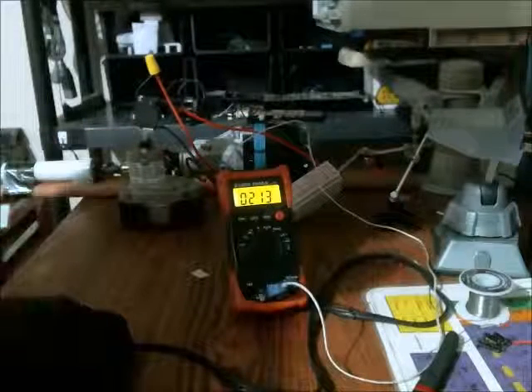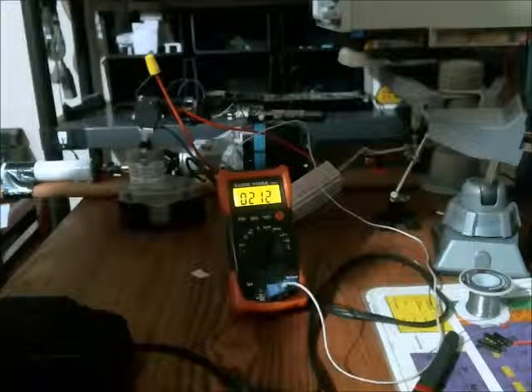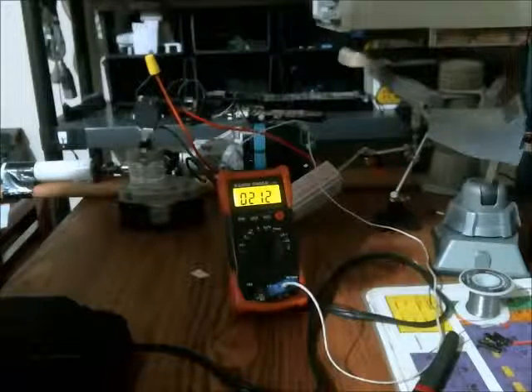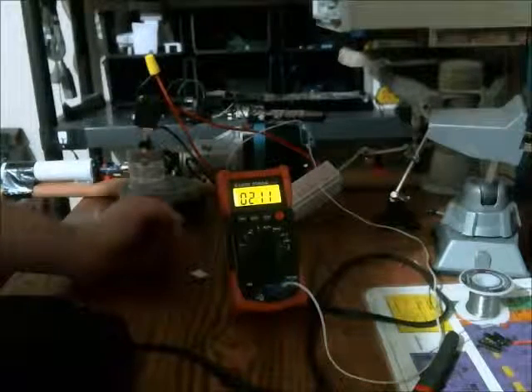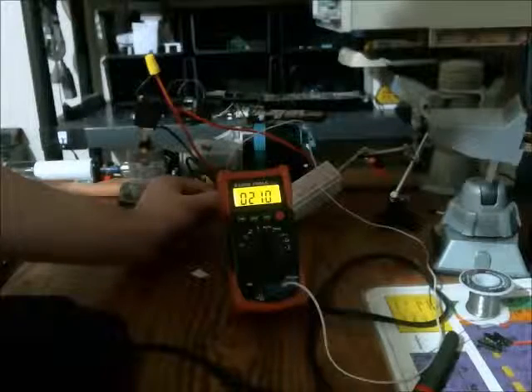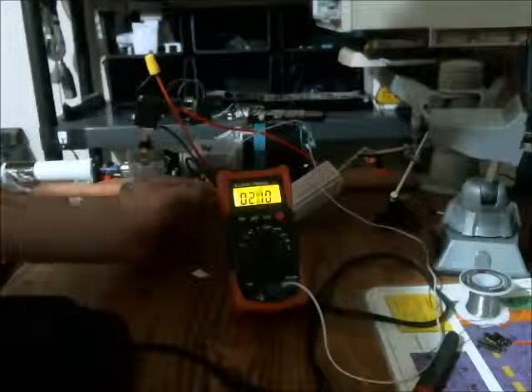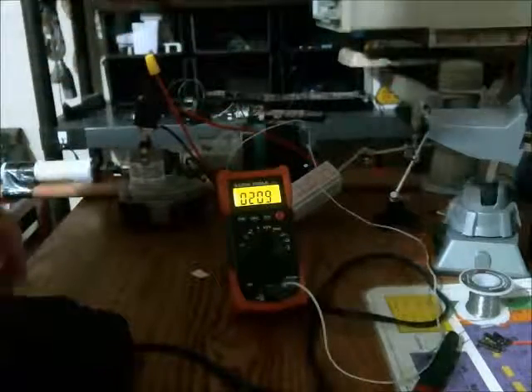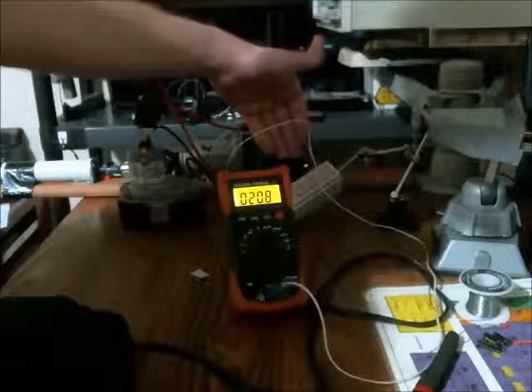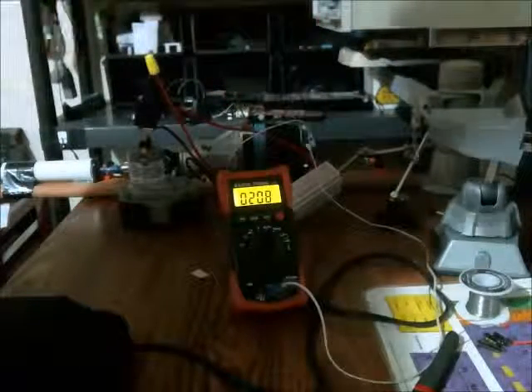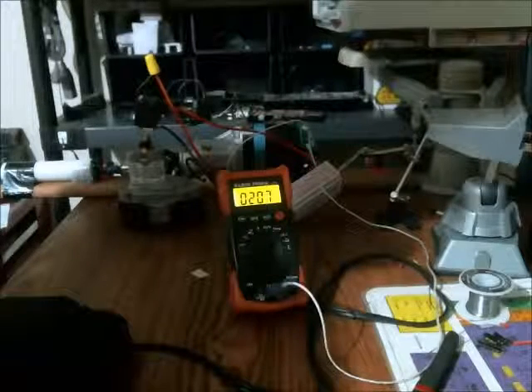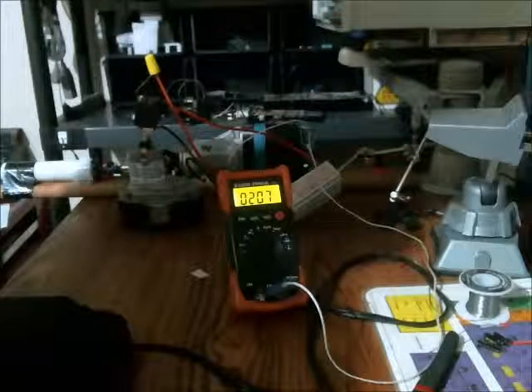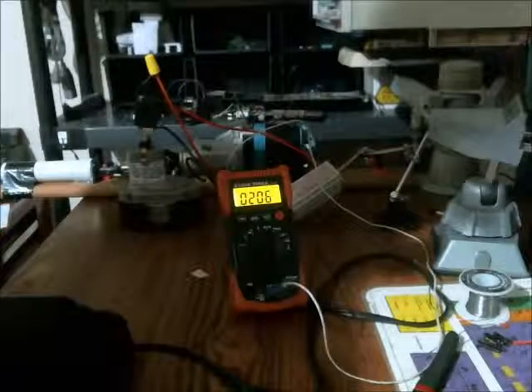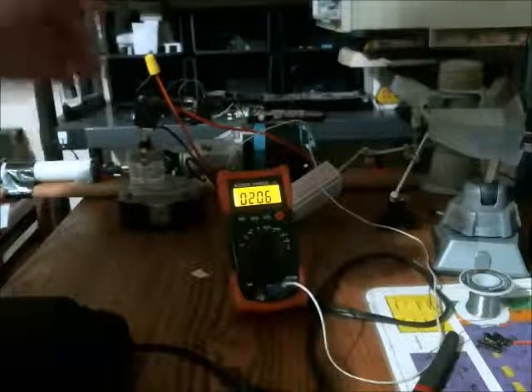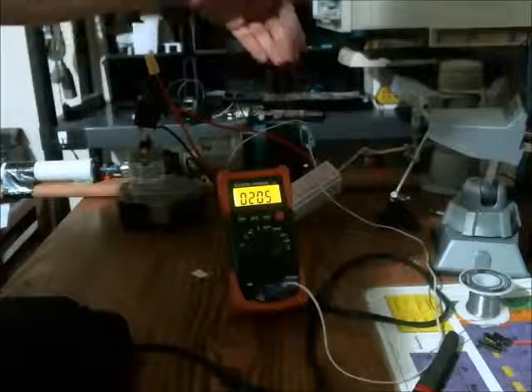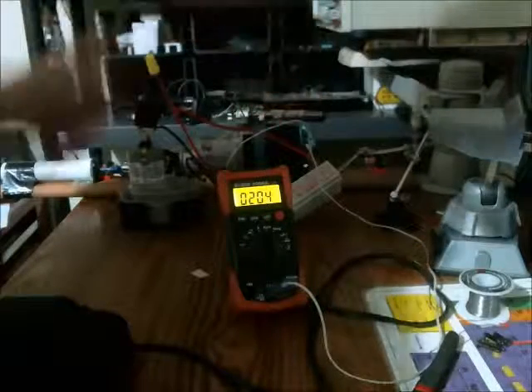Now, the temperature isn't dissipating quite as quickly as I would like, but it's pretty good. And if that temperature continues to be an issue, I can just increase the speed. And the faster the motor is going, the less voltage is seen across the IGBT, or less resistance, so less power will be dropped across the IGBT and more power will be dropped across the motor itself, so it won't get quite as hot.